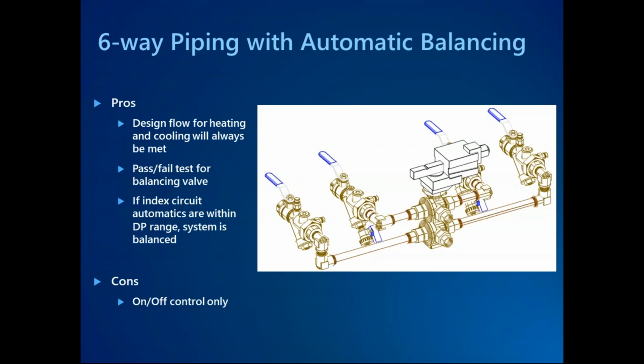The only real detriment to this type of solution is you can only really get on-off control when it comes to the six-way performance. That's because as the six-way begins to close off, the automatic balancing valve is going to try to counteract that. It sees a drop in differential pressure, so it's going to open up the spring and piston cartridge inside of the valve to try to maintain flow. So it's definitely a drawback, but in a lot of these low flow applications, all that might be specified is on-off control for the chilled beam zones, because again, the GPMs we're flowing through here are very, very low, and we don't see modulating specified nearly as much.